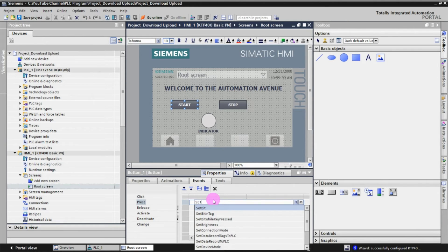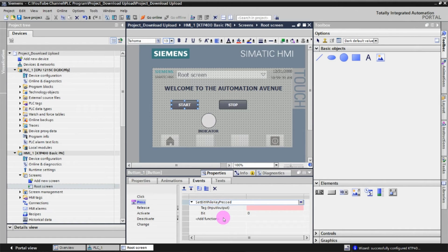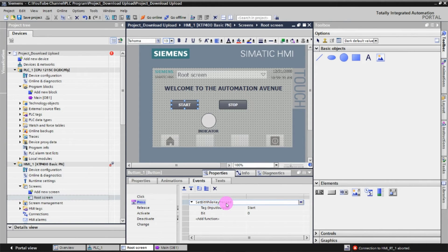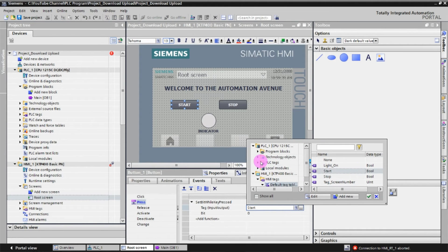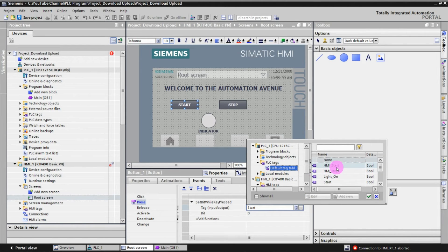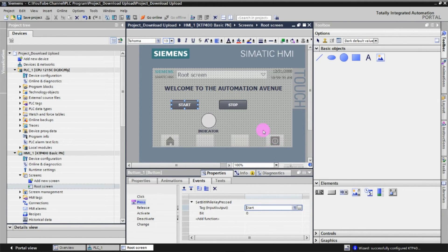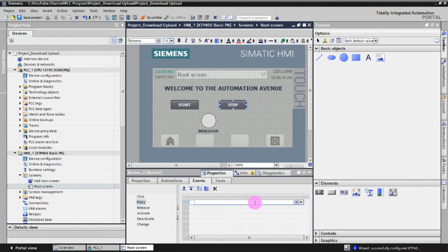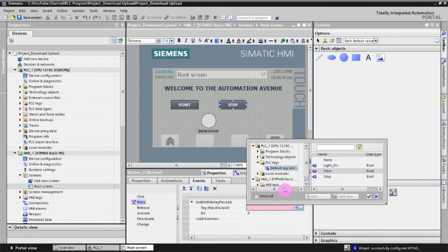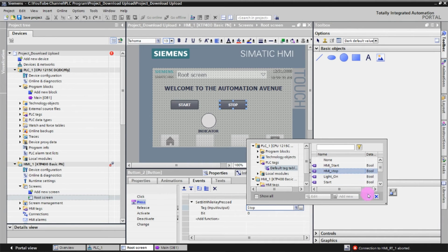Click on Press, then Add Function and select 'Set Bit While Key Pressed.' This means whenever you press the Start button the tag is set, and when you release it the tag resets. Click on the tag field, go to PLC Tags default tag table, and select HMI_Start, click OK. Do the same for the Stop button — click Press, add function, Set Bit While Key Pressed, go to PLC Tags and select HMI_Stop, then click OK.